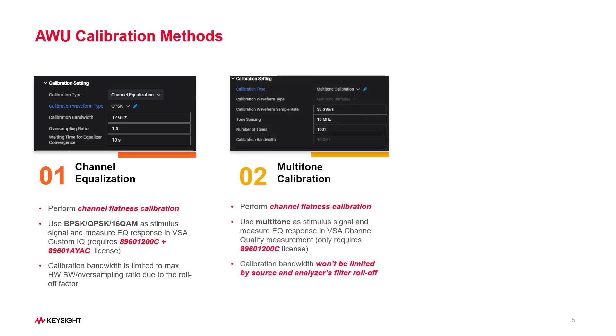The first is channel equalization, which utilizes VSA digital demod measurements for flatness calibration. The second is multi-tone calibration, which is used with VSA channel quality measurement, and it is ideal for frequency-band-edge flatness calibration.